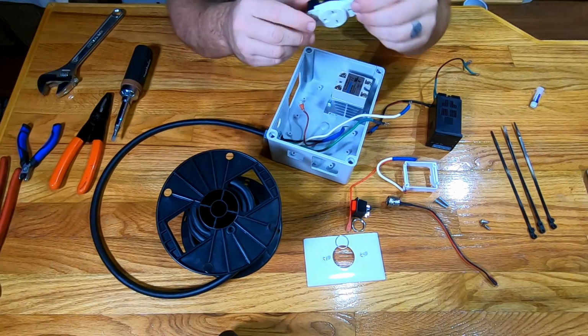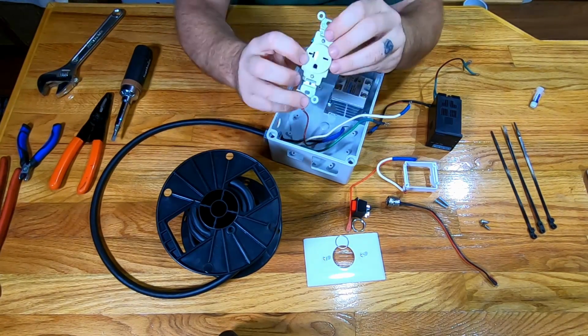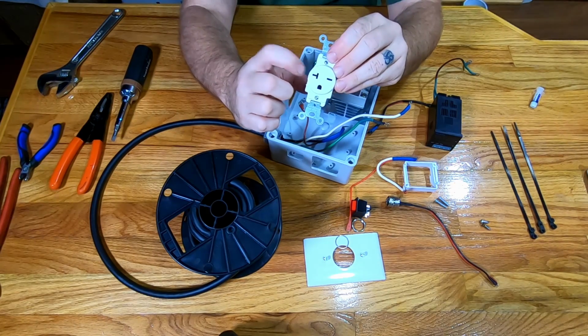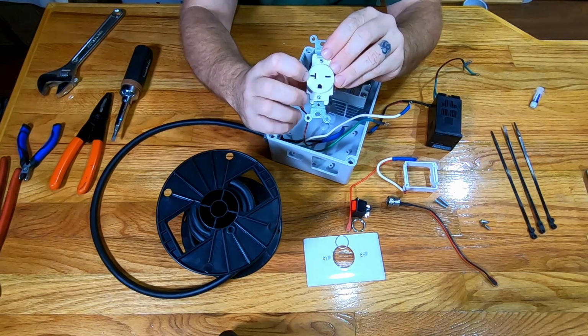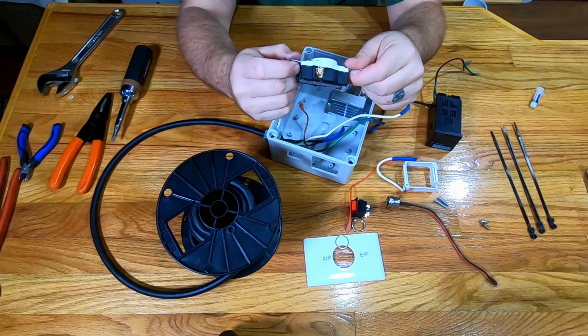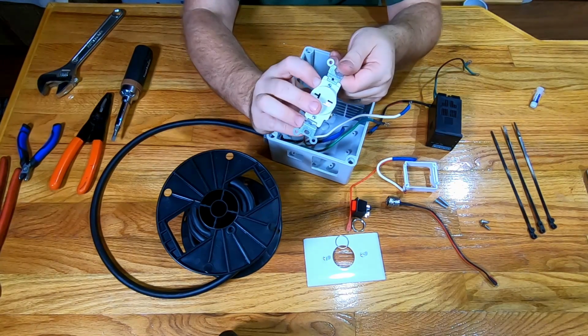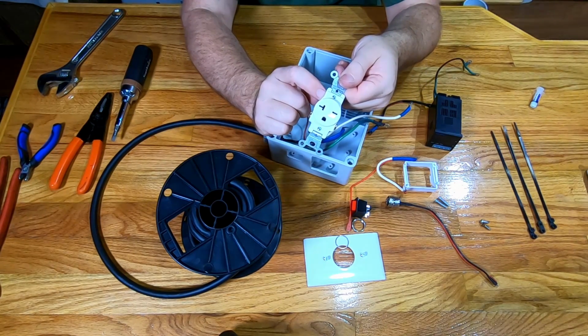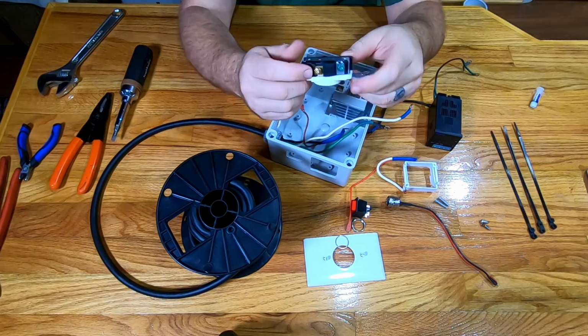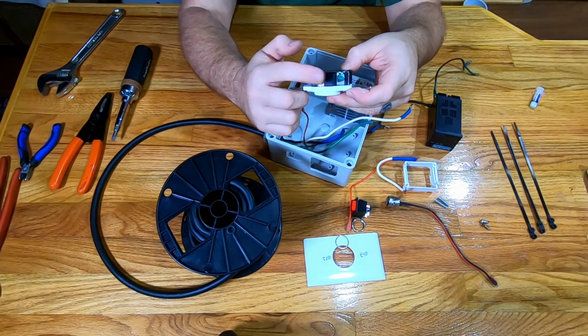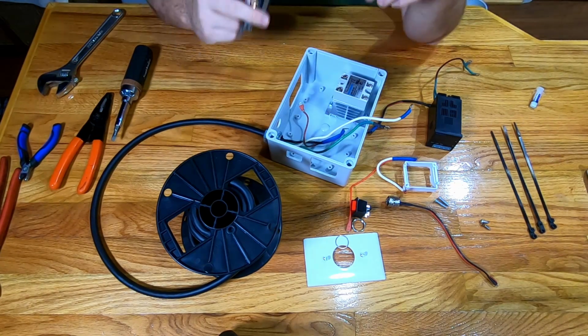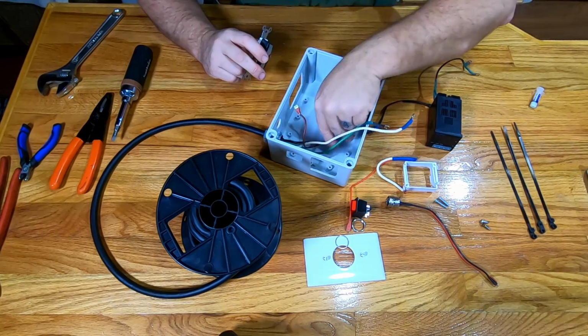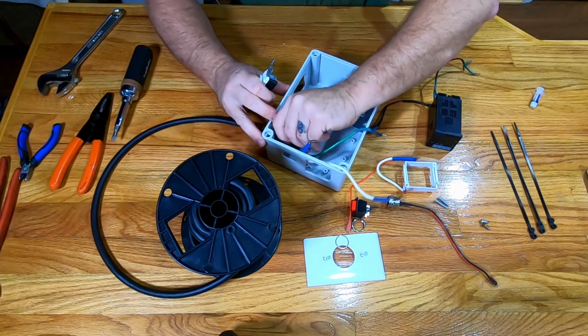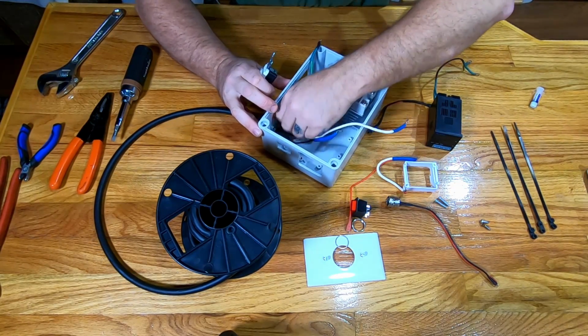Now, I know this looks like a household socket, but if you'll notice, it's got the little slot off to the side there. That tells us it's a 20 amp socket. I bought this as a 240 volt, which says 250 volt here on the receptacle. It's got 2 gold terminals instead of a gold and a silver. That's the important aspect here, to make sure we have a socket rated for the voltage and amperage we're going to be using.